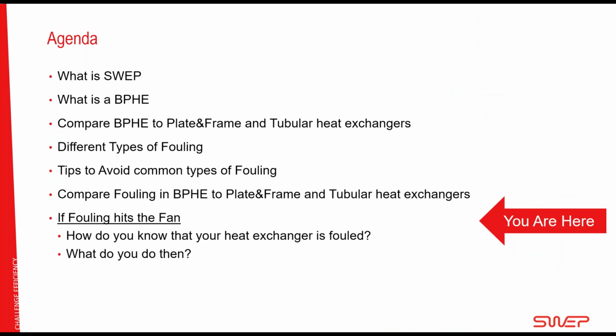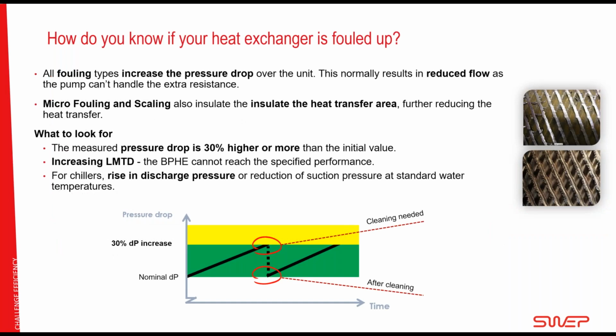So let's move on. If fouling hits the fan: now we have discussed what kinds of fouling there are out there, and how to avoid them with our best knowledge. But if fouling happens, what do we do? First, how do I know my heat exchanger is fouled up? What you should know now is that all fouling types increase the pressure drop over the unit. This normally results in a reduced flow, as the pump can't handle the extra resistance. So a higher pressure drop or lower flow in the system could be an indication of this. Microfouling, the suspended solids, and scaling also insulate the heat transfer surface, as we see here, clean and dirty. That will further increase the pressure drop, but it will also reduce the heat transfer.